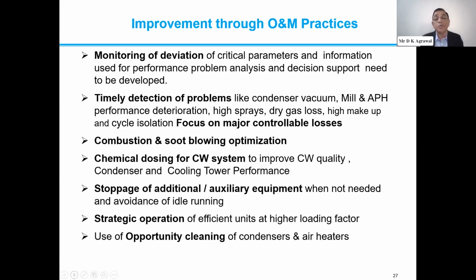So I think it is better to avoid those types of situations, because you have a limited type of tools available to remove these hard deposits. Otherwise, ultimately, the solutions are going to be chemical cleaning and all, which is not a very healthy thing. And if it is to be done very frequently, there is stoppage of additional auxiliary equipment, and that also has to be taken care of, particularly in the coal handling plant or in the milling system.